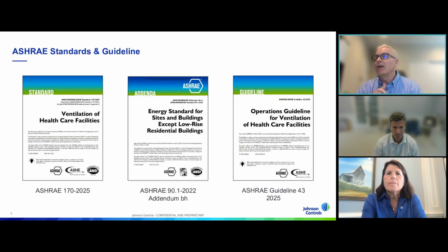And that's what we see there on that middle standard, which is ASHRAE 90.1. The last rendition is 2022. But what they recently did, and when I say recently, literally last month, is they added this addendum BH.